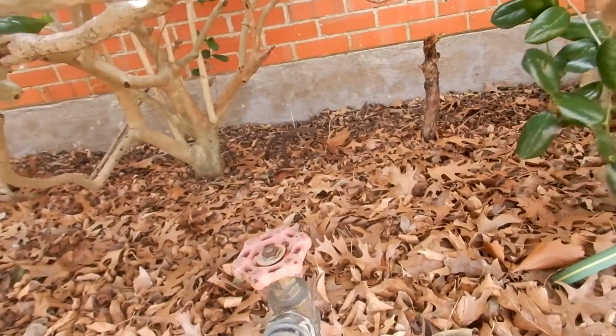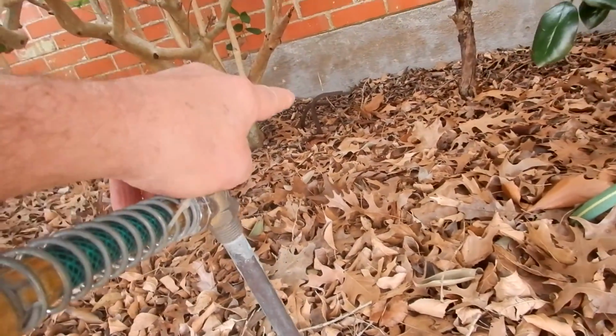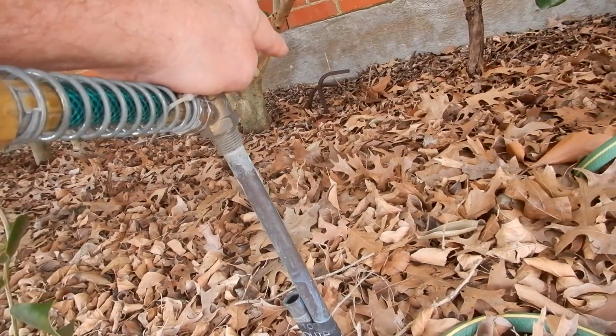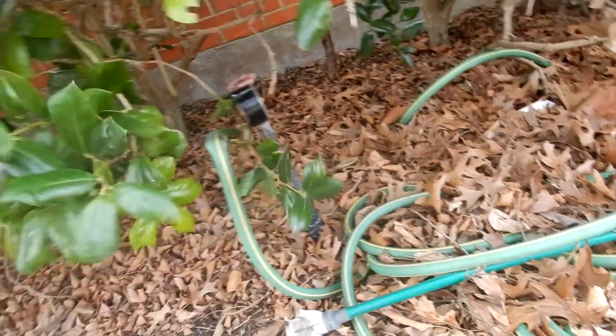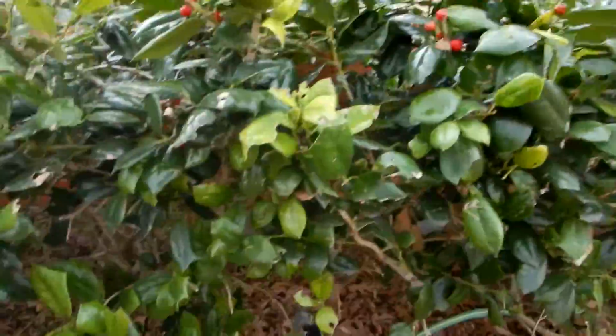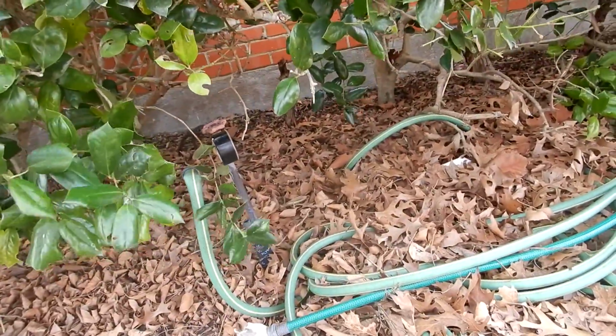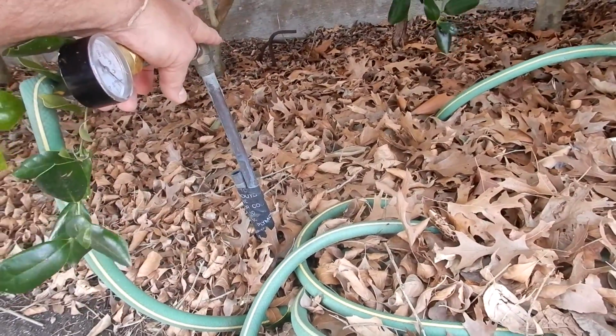This is the, right in here, see those little hooks over there? Those little hooks right over there? That is your main water shutoff valve. Those are old school. If you try to turn your water off using these valves, you're going to end up going back over to the meter and turning the water off. You're going to go inside the house and fix the problem that you had. And then you're going to come out here and you're going to dig these up, because these have failed on you, that's why you had to go out to the meter.